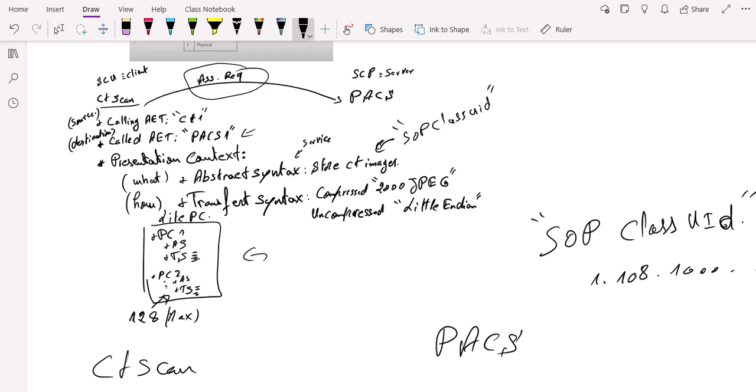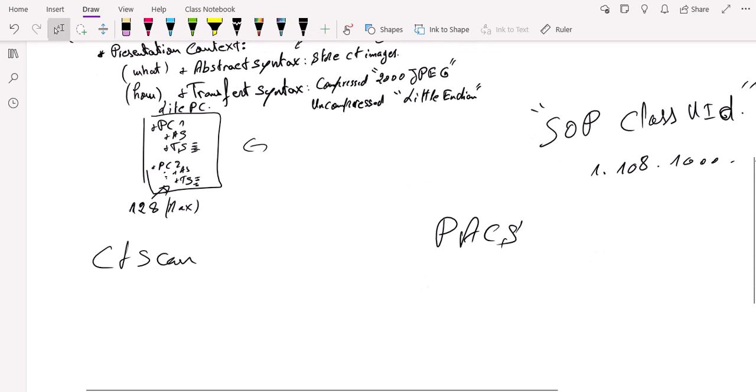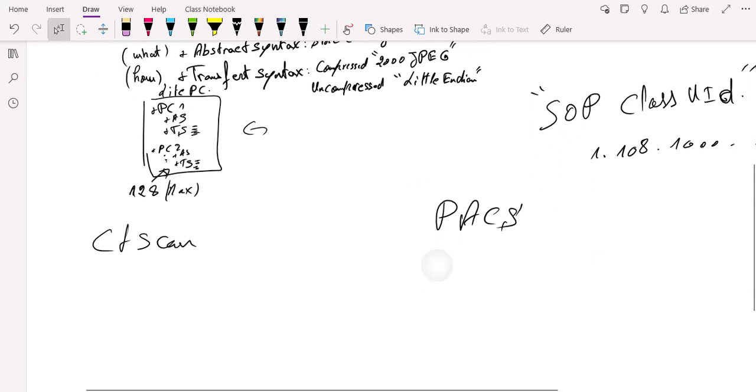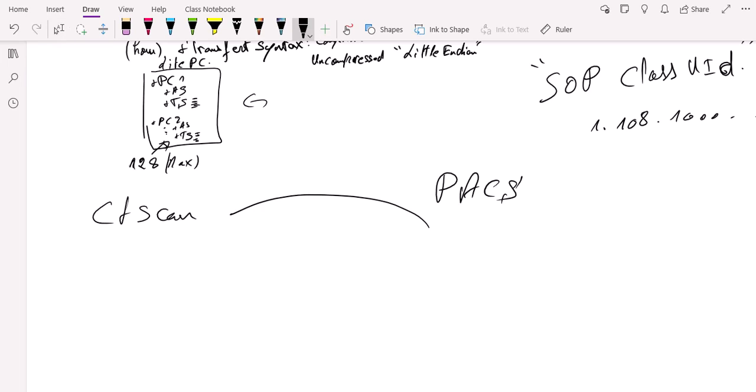You're going to send its UID. Even for these ways of transferring data, each transfer syntax has its equivalent UID. And here, the receiver, which is the PACS in our case, can look up the UID, and as a result, recognize which service is intended. And then the PACS responds with the supported services for each presentation context, and sends an association acceptance. So here, we're going to have an association acceptance.